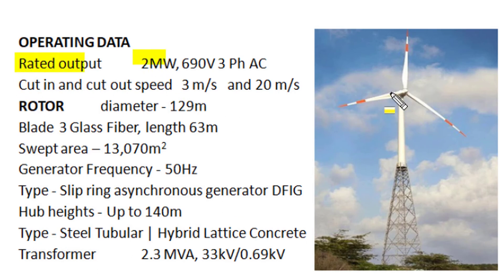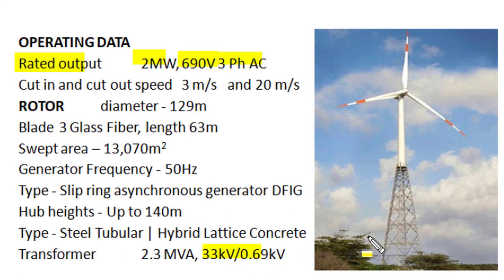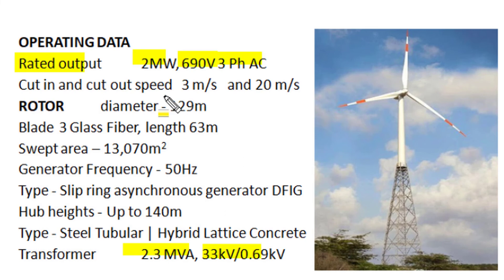Its rated output is 2 megawatts, and the generator produces three-phase alternating current at 50 Hz at 690 volts. This voltage is stepped up by the internal transformer placed in the nacelle to 33 kV for grid connectivity. The transformer rating is 2.3 MVA, in line with the rated output of 2 megawatts. The cut-in speed is 3 meters per second and the cut-out speed is 20 meters per second, so within this speed range it can produce electrical output effectively.